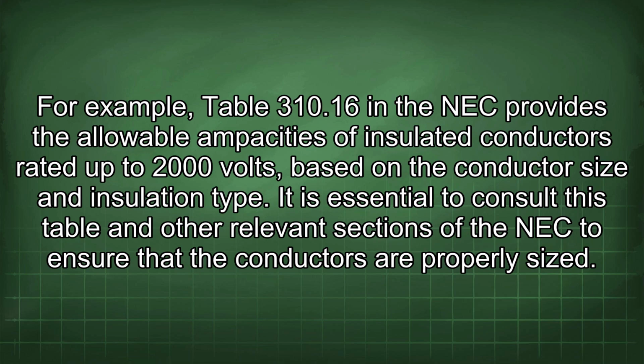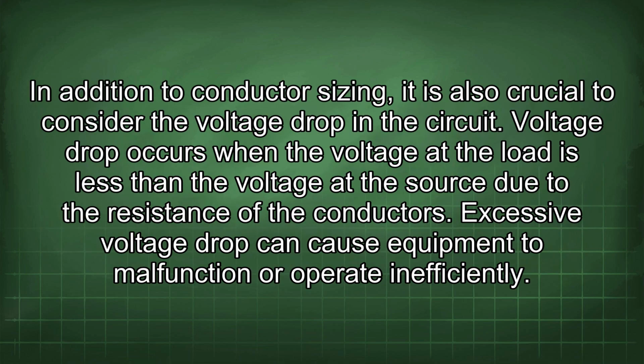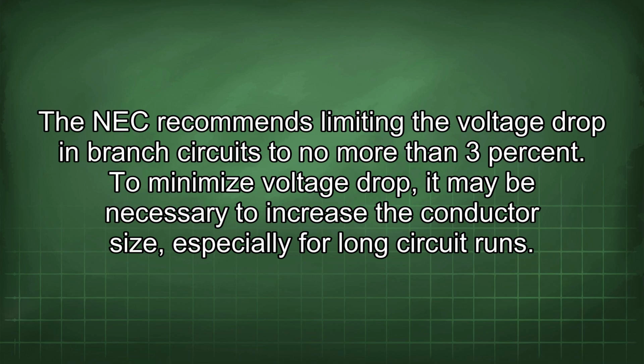It is essential to consult this table and other relevant sections of the NEC to ensure that the conductors are properly sized. In addition to conductor sizing, it is also crucial to consider the voltage drop in the circuit. Voltage drop occurs when the voltage at the load is less than the voltage at the source due to the resistance of the conductors. Excessive voltage drop can cause equipment to malfunction or operate inefficiently. The NEC recommends limiting the voltage drop in branch circuits to no more than 3%. To minimize voltage drop, it may be necessary to increase the conductor size, especially for long circuit runs.